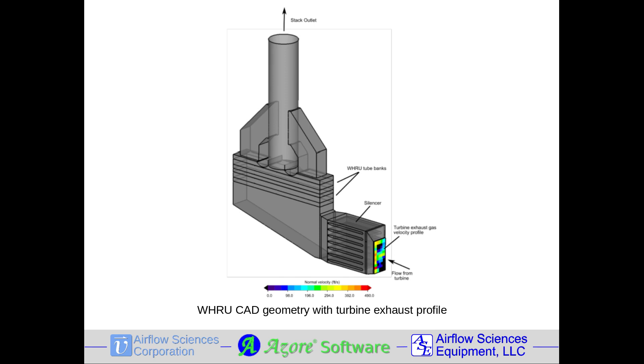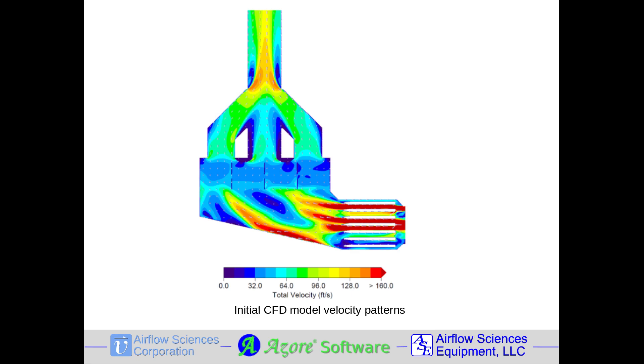In this case study, the turbine exhaust velocity profile was highly stratified, as seen in this figure. Initial CFD model results confirmed that the velocity patterns inside the unit were highly skewed through the silencer and significantly stratified as the hot turbine gases approached the tube bank.